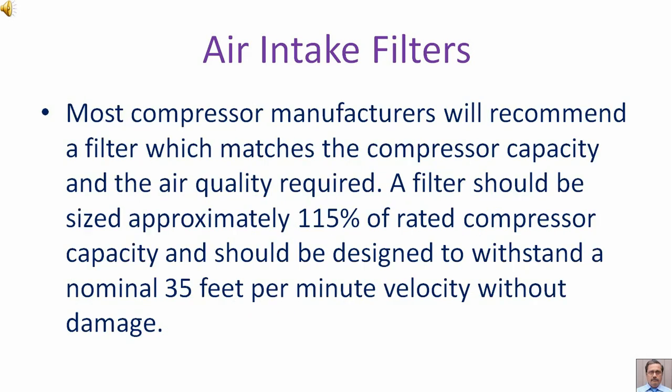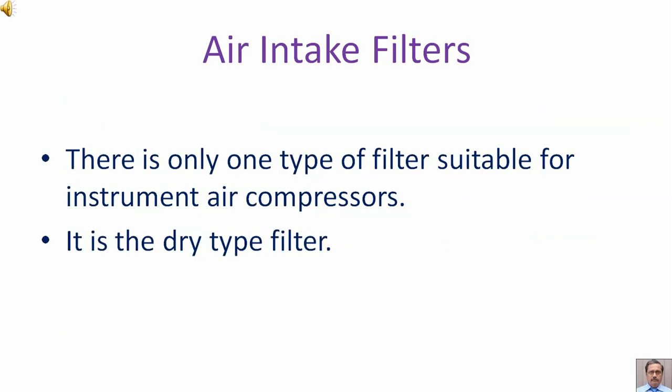Most compressor manufacturers will recommend a filter which matches the compressor capacity and the air quality required. A filter should be sized at approximately 115% of rated compressor capacity and should be designed to withstand a nominal 35 feet per minute velocity without damage. There is only one type of filter suitable for instrument air compressors — it is the dry type filter.